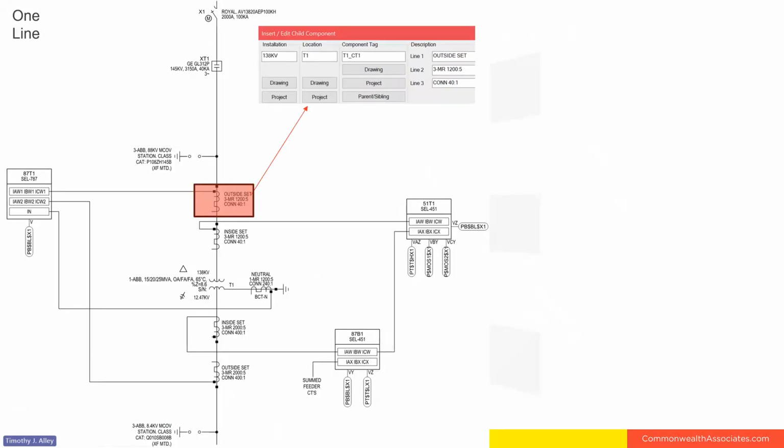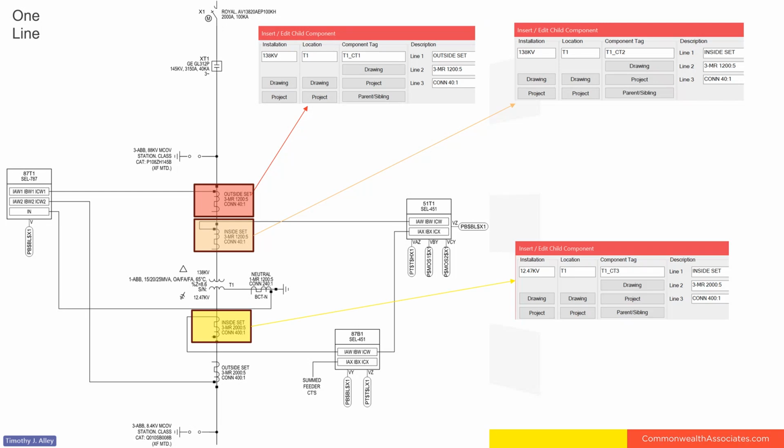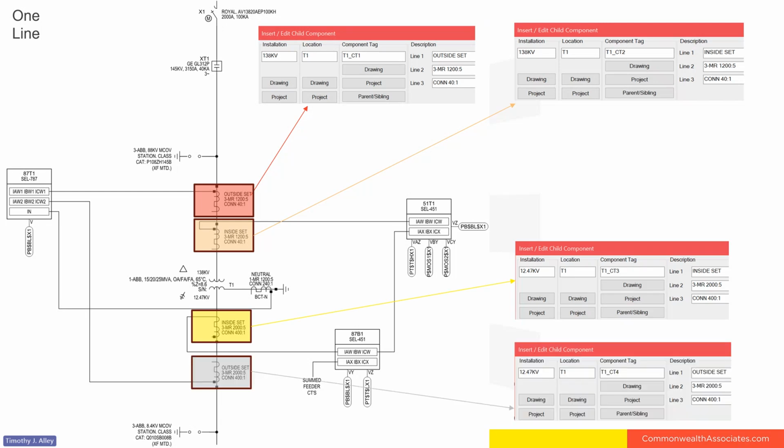So in the P&C world, the one line is the roadmap. It's what we always start from. It's where the drawings begin. And here I took the CT and I identified it as being part of transformer one. And then the first CT, I just labeled it CT1. And then the data that I want to show on the one line is in the description fields. And I did the same for the CTs, just naming them sequentially.